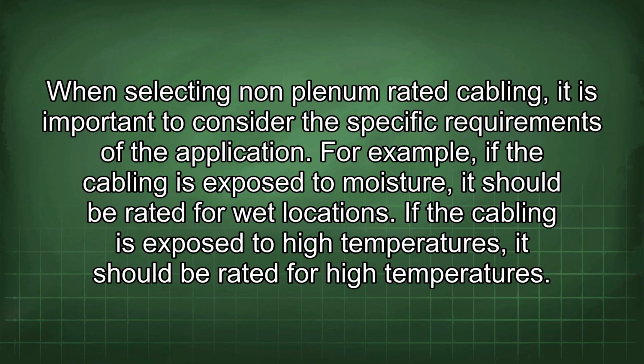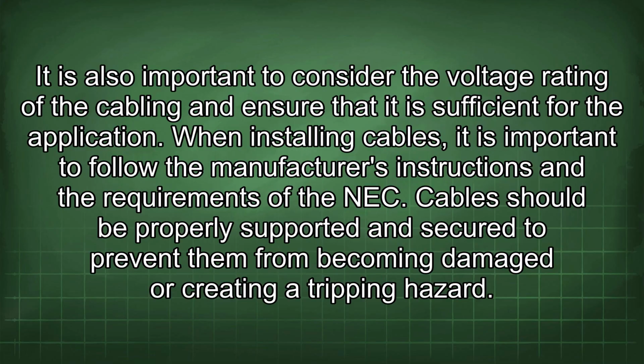For example, if the cabling is exposed to moisture, it should be rated for wet locations. If the cabling is exposed to high temperatures, it should be rated for high temperatures. It is also important to consider the voltage rating of the cabling and ensure that it is sufficient for the application. When installing cables, it is important to follow the manufacturer's instructions and the requirements of the NEC. Cables should be properly supported and secured to prevent them from becoming damaged or creating a tripping hazard.